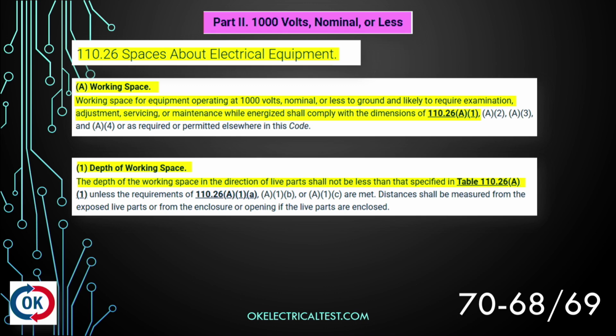So they're saying, hey, I need to not only comply with A1, which is the depth of the working space, but also A2, which is the width, and then A3, the height. So everything that's listed in here, we need to comply with all of that, not just one of the regulations. We're going to look specifically at A1, which is the depth of the working space. I call that the belly room, right? How much belly room do we need to have? It says, hey, if we're looking for the depth of the working space, refer to table 110.26(A). And so we're going to take a look at that here next.